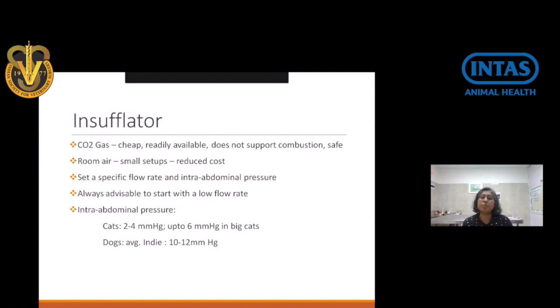Now, when you start inflating the abdomen, which is the basic step to start off with your laparoscopy, you need to set a specific flow rate and an intra-abdominal pressure. The abdominal wall can only distend to a certain limit and not more than that. More than that, it will only cause complications. So it's always advisable to start the flow slowly. Whatever carbon dioxide is getting infused into the abdominal space goes in slowly and reaches that threshold slowly. During this time, since the patient is under general anesthesia, you have to observe the SpO2. In some cases, if the flow rate suddenly increases, it can cause a drastic reduction in your SpO2. If you're a single operating surgeon, from a practical point of view, this is very alarming because your monitors are continuously beeping. You wouldn't know whether to abort the surgery or not.